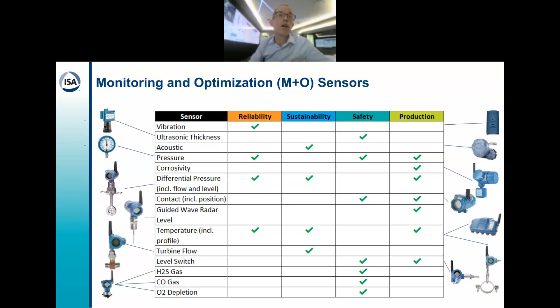Many wireless sensors come with an associated app, but that's not sufficient. You also want to get some of the measurement data into third-party analytics and other software. For some use cases, you also want to get the data into the DCS or historian because operators need to know. The wireless gateway must make measurement data available as OPC UA, Modbus, and HART IP.